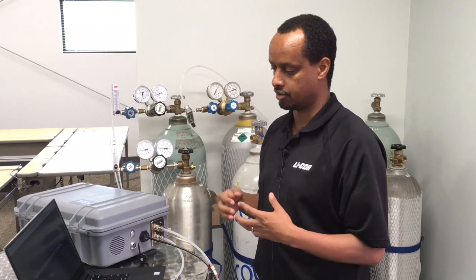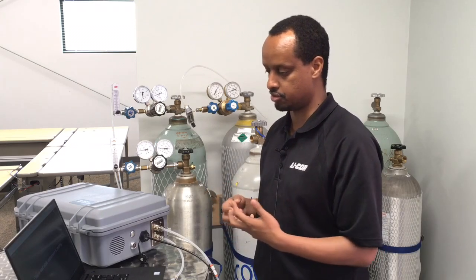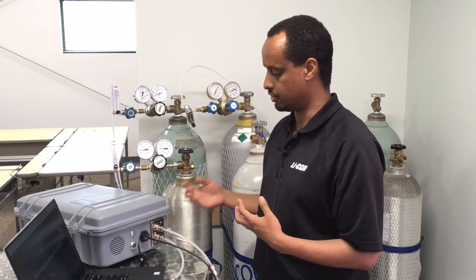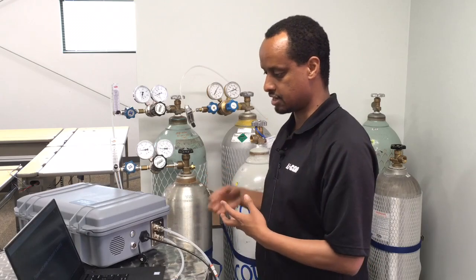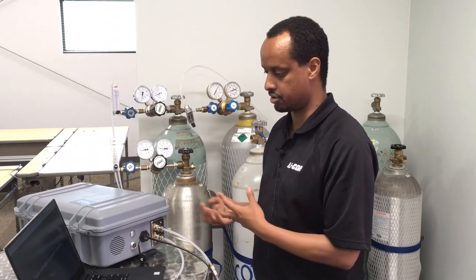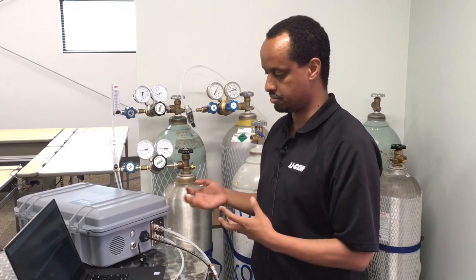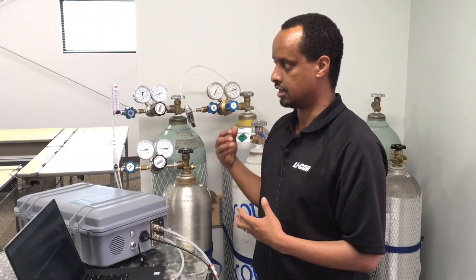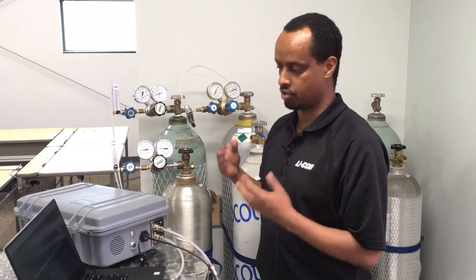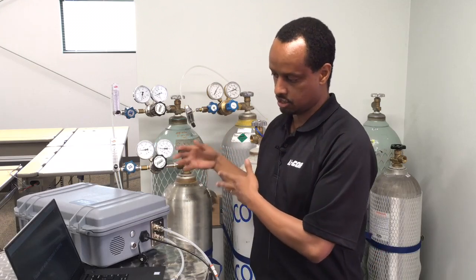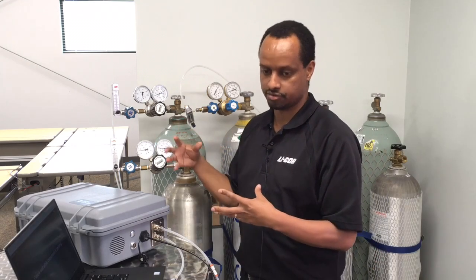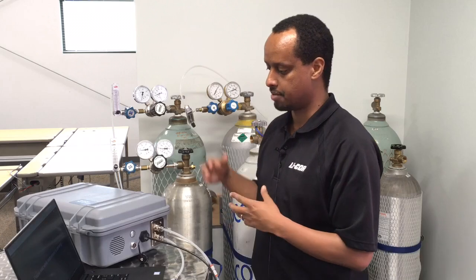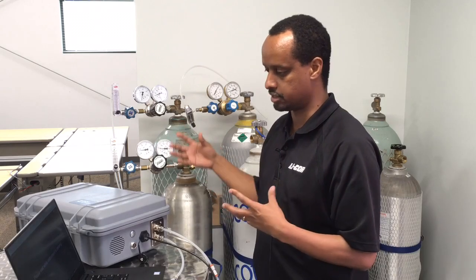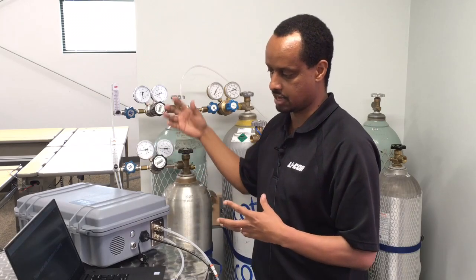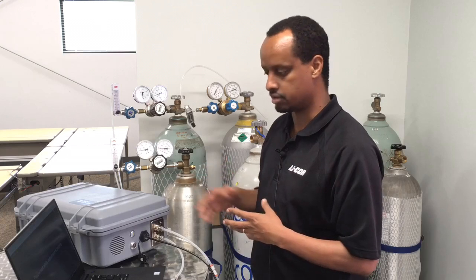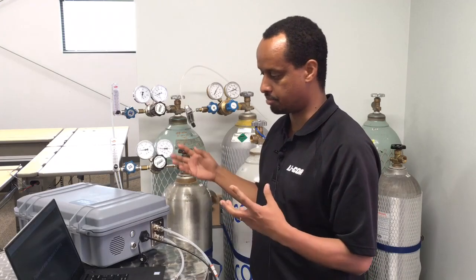And we see that in the instruments that we produce. We do the testing here, and we see that in the instruments that we test after manufacturing and production, all of them meet that specification. In fact, that specification doesn't mean 1 ppb per day continuously or a cumulative spec. It's 1 ppb per day, but it doesn't add up. So over several days, we don't expect over 10 days 10 ppb. It hovers around 1 or 2 ppb over a month.